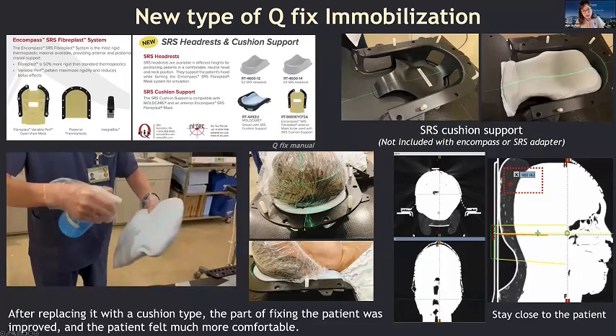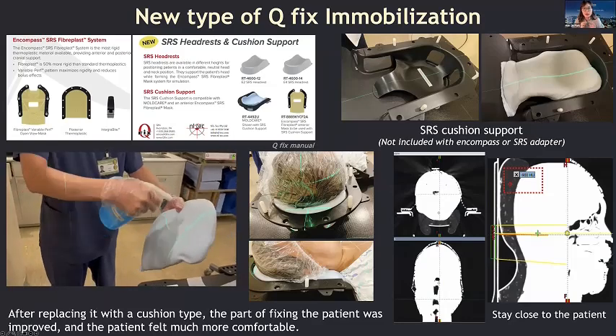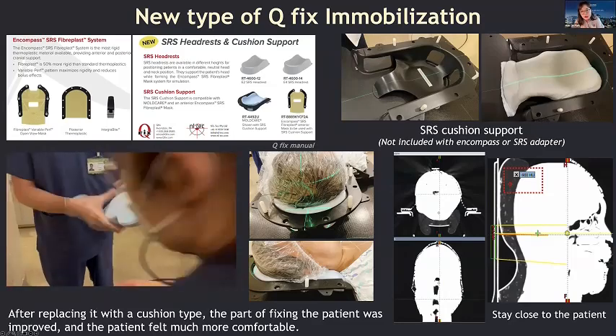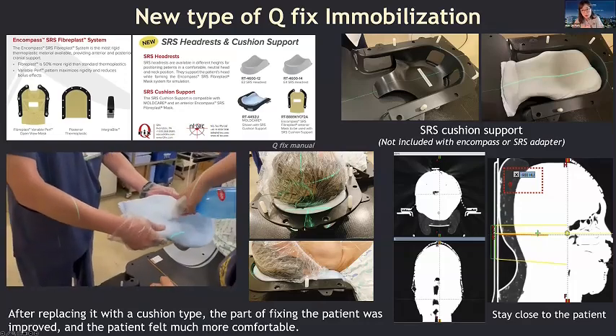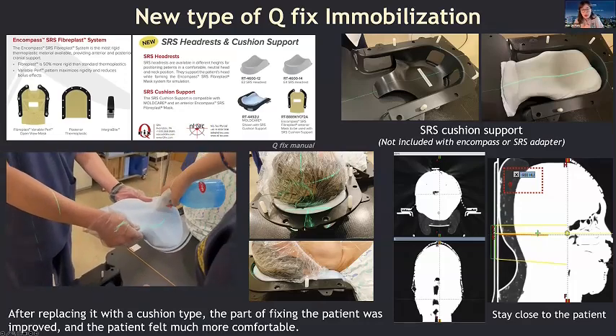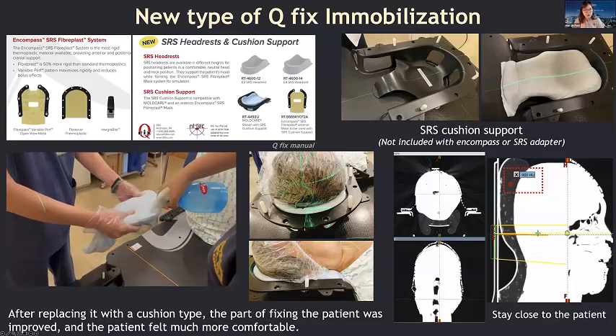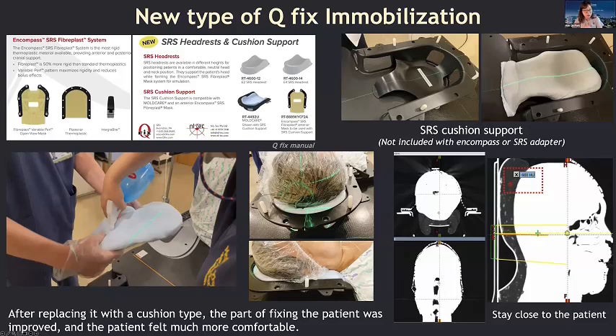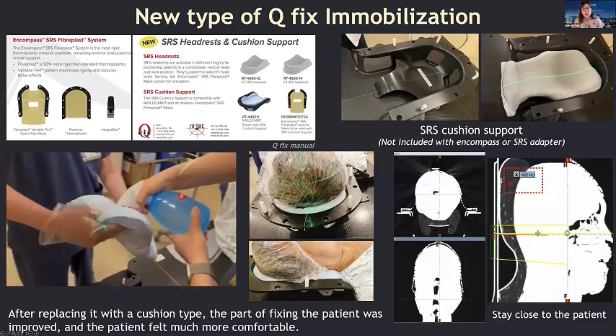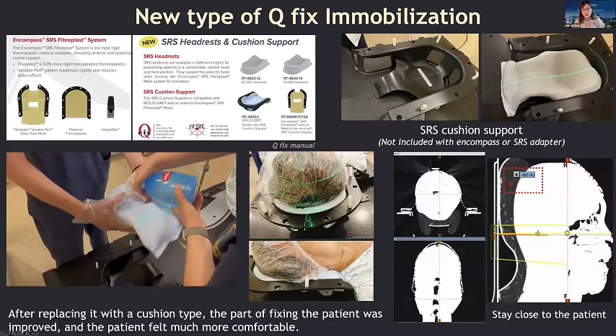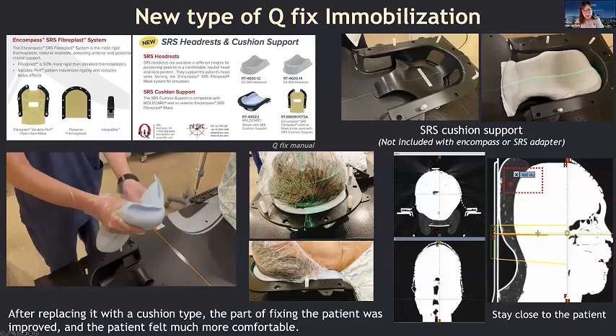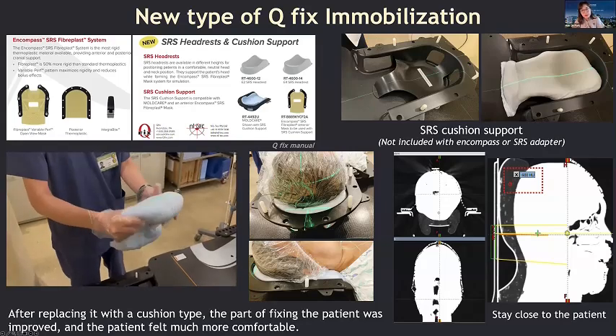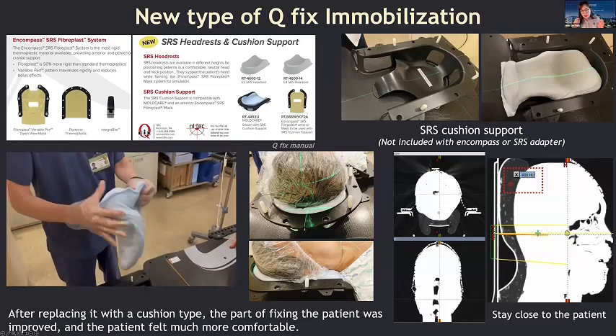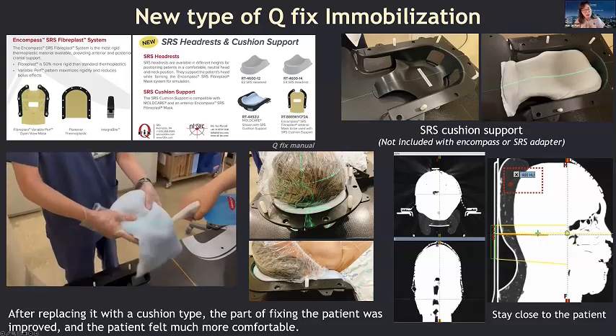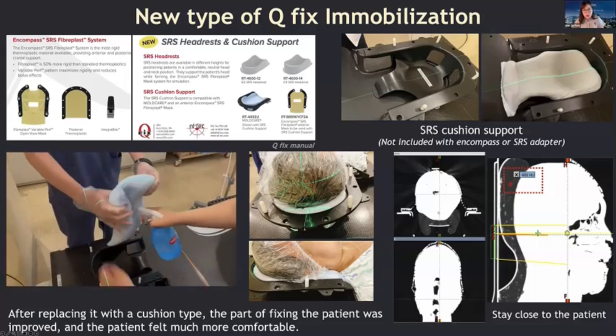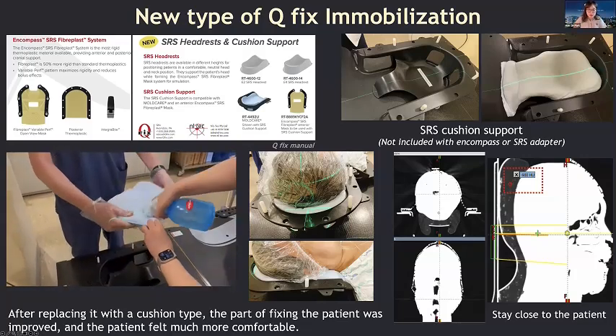Due to these overall limitations, the QFix team released a version that can be fixed using the cushion type, and they received official approval from Varian a while ago. After replacing it with the cushion type, the fixing of the patient improved greatly, and the patient felt much more comfortable than before. I was worried about the cushion material for SRS treatments, but when I took a CT scan measurement, I could see that it had a density similar to air, at -800 HU on average. So we changed everything to the cushion type at the moment.